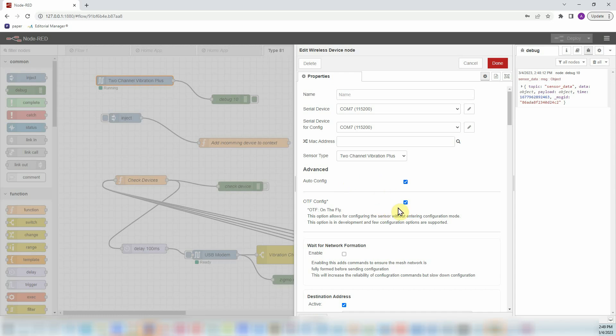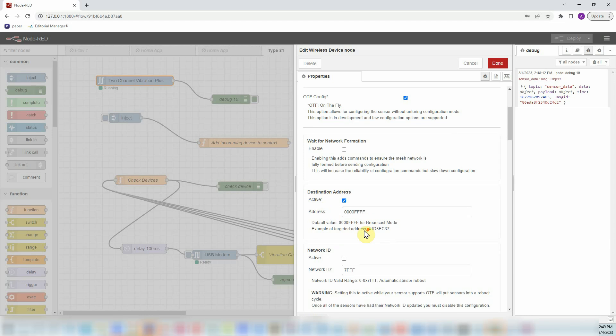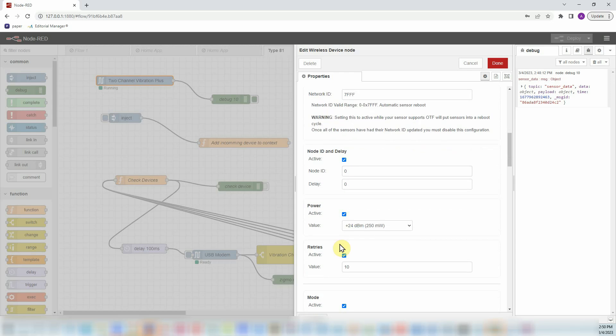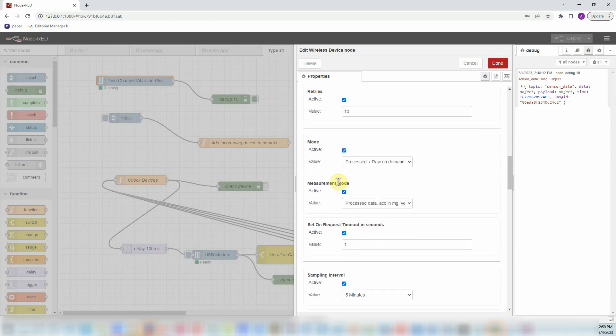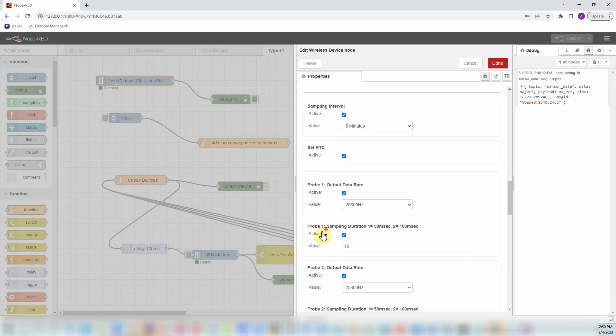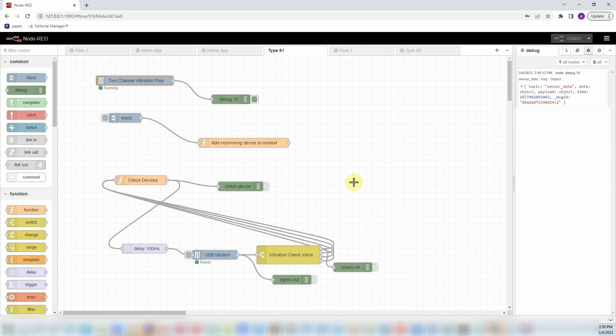The good thing about this is that you don't have to push the buttons. You can have it remotely installed and you can still configure the settings. In this case I'm gonna change where I want to send data, my node ID and delay. Delay should always be zero. My power, retries, mode, processor data, measurement mode, and all these settings. Once I do that, I'm gonna click done and I'll press reset.